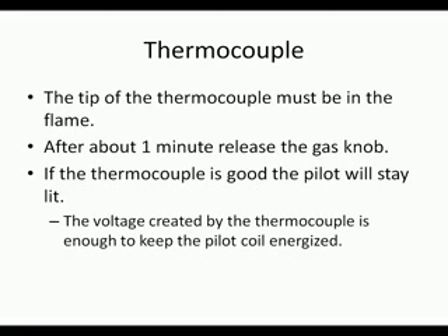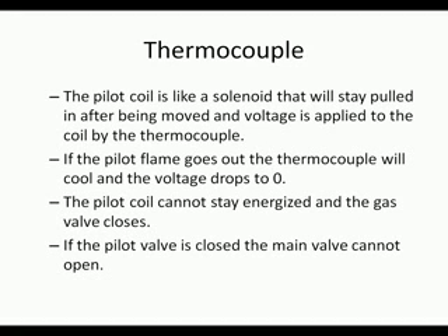When the gas has been off for 5 minutes, you can turn these gas knobs to pilot position and push the knob down. Pushing the knob down opens the pilot gas valve. Light the pilot. You must hold the knob down until the pilot is lit and the thermocouple is hot. The tip of the thermocouple must be in the flame. After about 1 minute, release the gas knob. If the thermocouple is good, the pilot will stay lit.